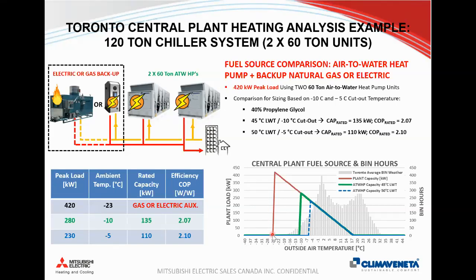So this is actually taking into account the part load operation of the heat pumps, and it's also taking into account the decreased COP from having 40% glycol in the system, which is a typical requirement that we'll talk about later. So we still have a COP in this scenario of about 2.1 or 2.07, depending on the temperature.